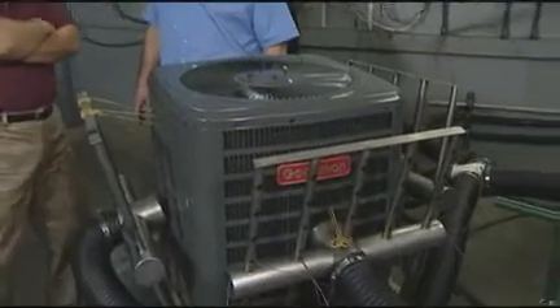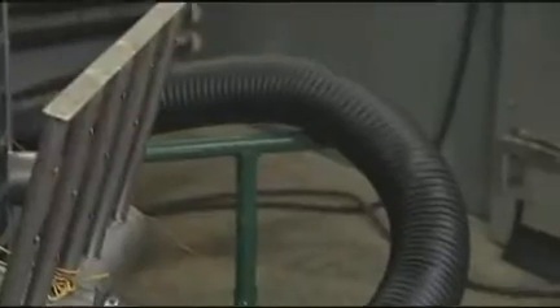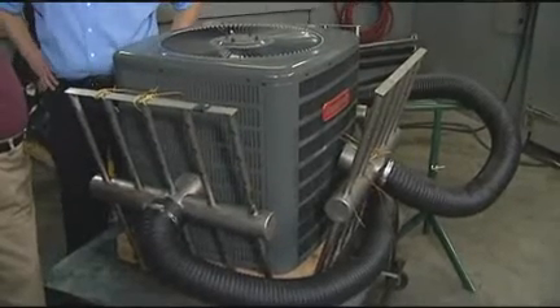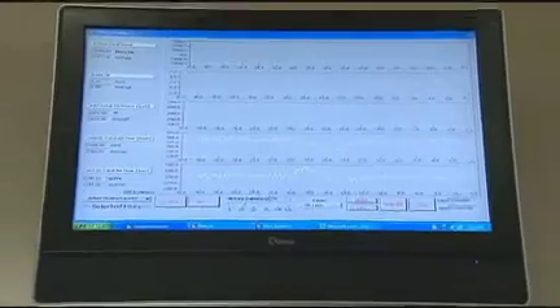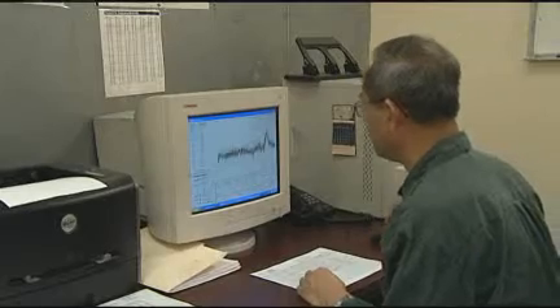What are all these extra things on it here? Well, these are stainless steel sampler trees positioned around the inlet side of the condenser coil. These are for measuring the inlet air dry bulb and wet bulb temperatures entering this particular heat exchanger. In this lab, we need to operate this product under a wide range of operating conditions so that we can measure capacities, efficiencies, SEER ratings, and HSPF ratings. Do you literally take the temperature to different extremes? As high as 135 degrees and well below zero.